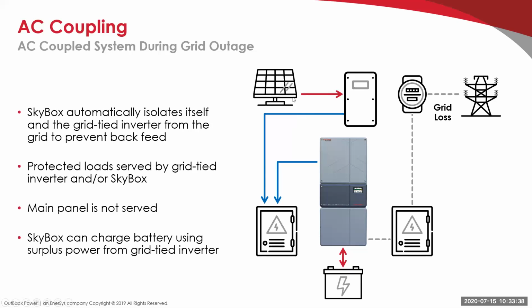Now, if the grid-dependent inverter produces more energy than what's needed on the backed-up load panel, that extra energy comes back, since we're in inverting mode, as an unregulated charge onto the batteries—because we're regulating voltage at this point, not current. That's why we have protections in place to protect the battery from being overcharged.